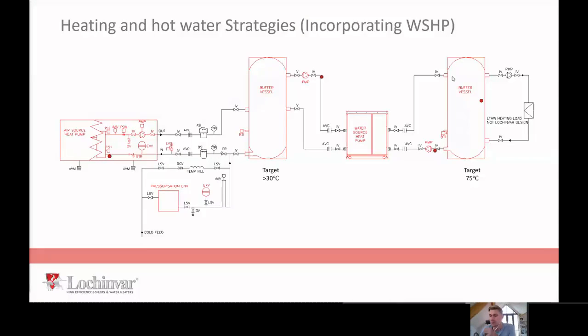And if you turn down that temperature, you increase the overall efficiency again, because when you put compressors in series, it's doing the same equivalent work of one compressor not in series, which means that flowing at 60 degrees versus a heat pump flowing at 60 degrees, your actual efficiency is going to be very comparable. So this is like a future-proof style design for an application where you can't flow at a low temperature yet, but you might in the future. Or even if you don't in the future, it's still going to work.